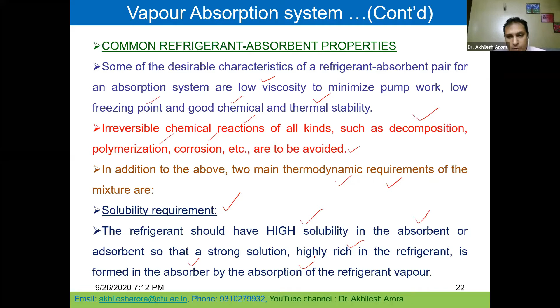Then there is the boiling requirement. Once this strong solution is formed with the help of the refrigerant and the weak solution which is coming from the generator, it should also be easy to separate, and for that we have a boiling point requirement. There should be a large difference in normal boiling point of the two substances, at least 200 degrees Celsius. So this is very, very important. This temperature difference should be 200 degrees Celsius so that the absorbent exerts negligible vapor pressure at the generator temperature. Thus, almost absorbent-free refrigerant is boiled off from the generator and the absorbent alone returns to the absorber.